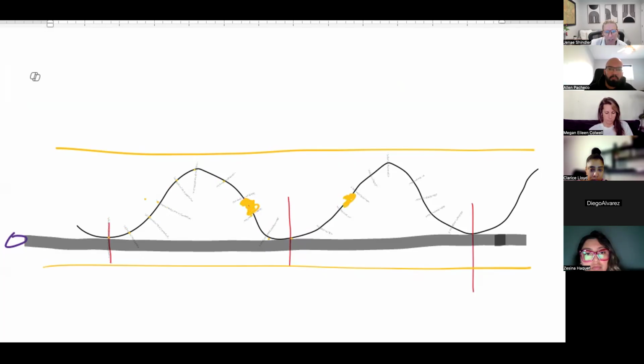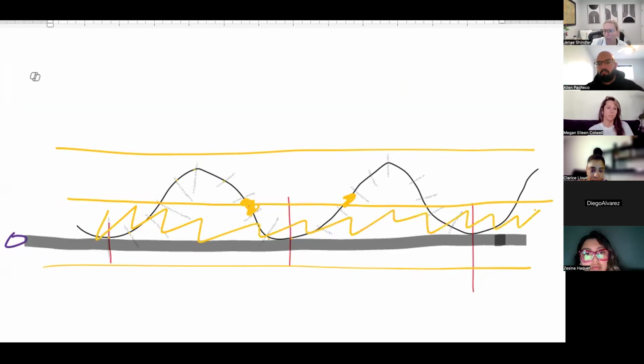They'll be right about here. So what they're saying is 70 to 30% of that wave sits right about here. And as long as it's in this category, which is the expiration portion of a natural breath, that is when it'll beam on. So when your physicist says, or your prescription says, we're treating 70-30, we know on that wave, we're treating the lower portion, the expiration portion of the breathing.